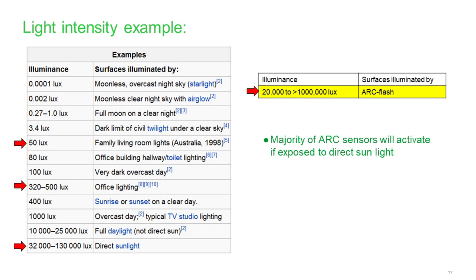Regarding sensitivity: 50 lux is similar to light in a family room; office lighting is 300 to 500 lux; direct sunlight is 32,000 up to 130,000 lux. Arc flash produces 20,000 up to 1 million lux — something close to sunlight. Most arc flash sensors will activate if exposed to direct sunlight. So the arc flash is very intense light and can easily operate all of these sensors.